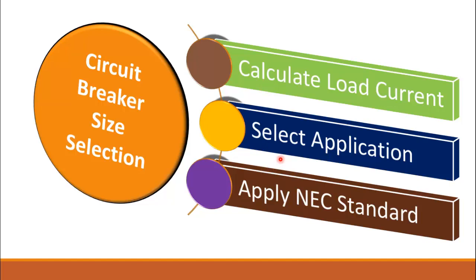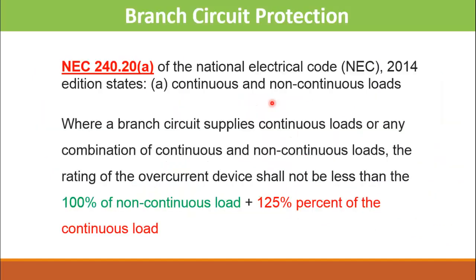Selecting the type of application means identifying which type of load we require protection for. For example, there are resistive loads such as lighting and resistors, and there are inductive loads such as motors. Once we select our application, the last step is to apply the NEC standard, which classifies the selection of circuit breaker according to the type of application. In this video we will learn how to size the circuit breaker for resistive loads, or loads other than motor loads.